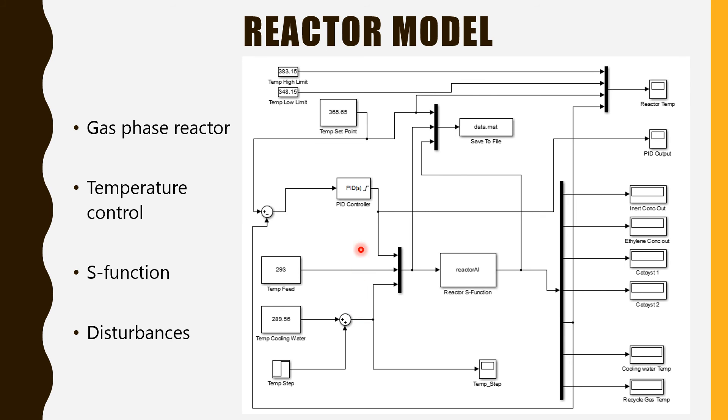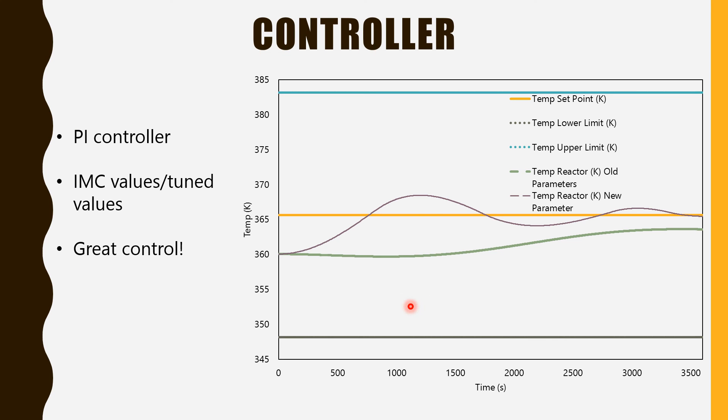So, what we did is we built a step test to the system, we fit it to an FOPDT model, and using the IMC correlations, we found constants for our PI controller.